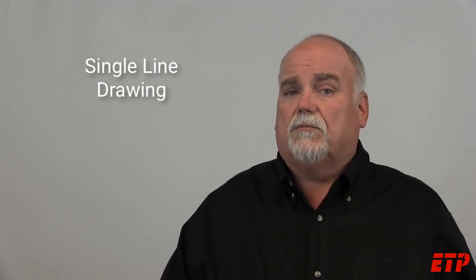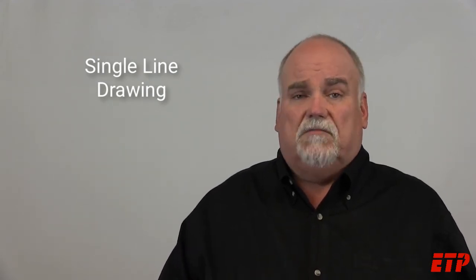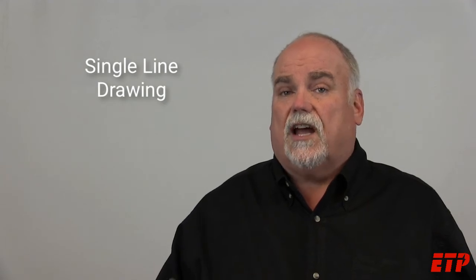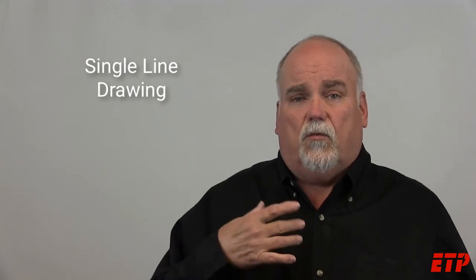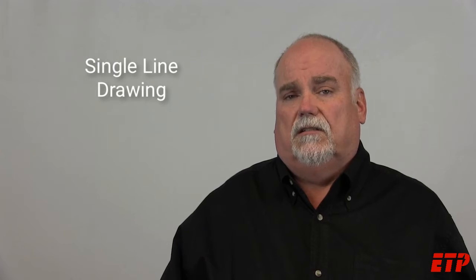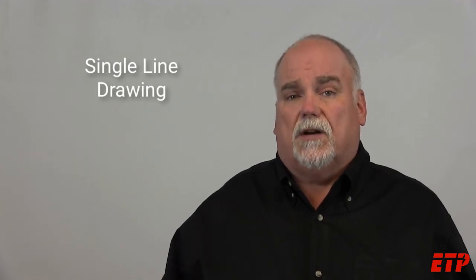They're a tremendous help to contractors, to engineers trying to design things. It saves a lot of time, and it makes all these people safer as they go about their job. The single line drawings are required to be kept up to date by Chapter 2, Article 205.1 in 70E. It says if you have these drawings, you must keep them up to date and keep them legible.